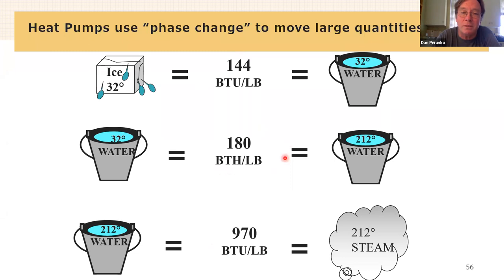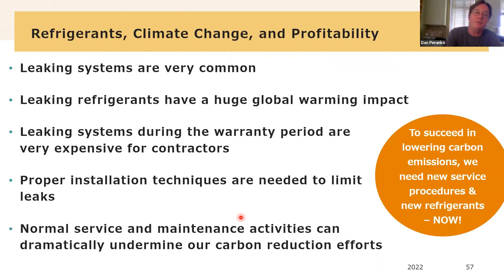So small BTU input or output to change the temperature, huge BTU input or output to change phase, to change state from liquid to gas. And that's the underlying principle that allows these things to work. And we're not burning anything and we're not using methane, right? So all huge benefits as long as the refrigerant doesn't leak.